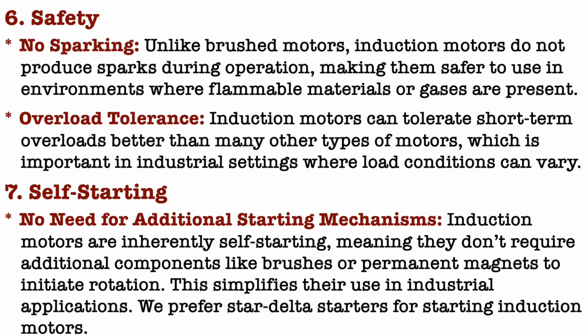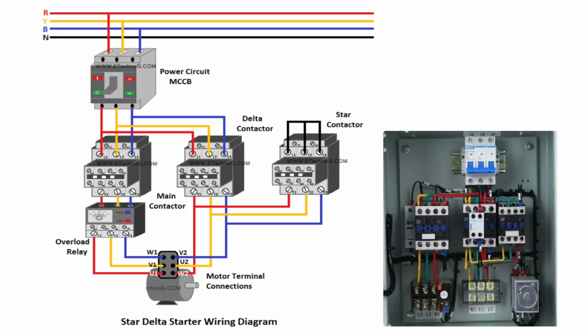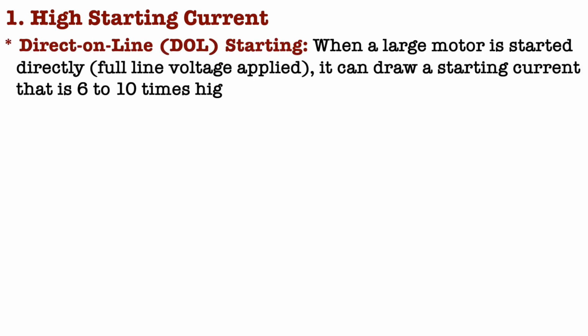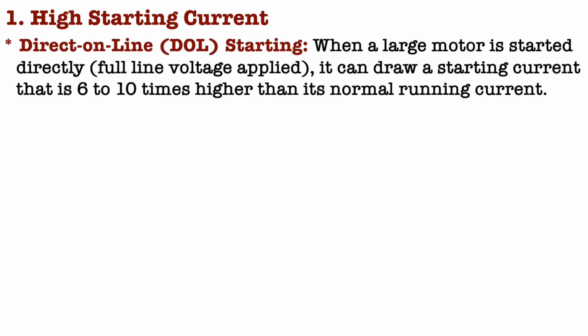We prefer star delta starters for starting induction motors. These starters are essential due to the following factors. First one is high starting current. When a large motor is started directly, it can draw a starting current that is 6 to 10 times higher than its normal running current.